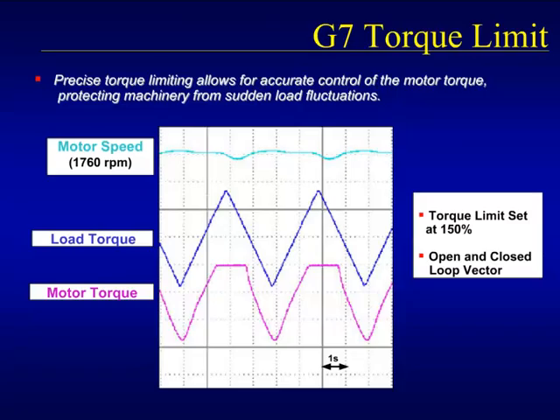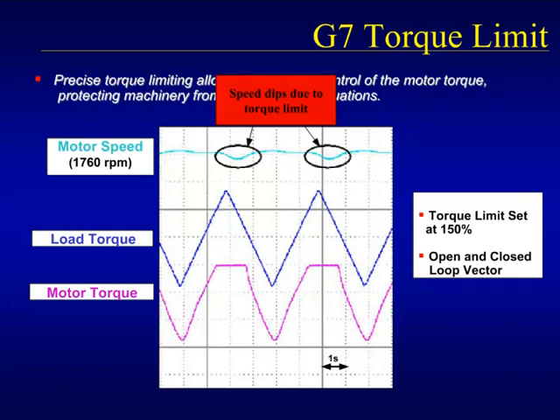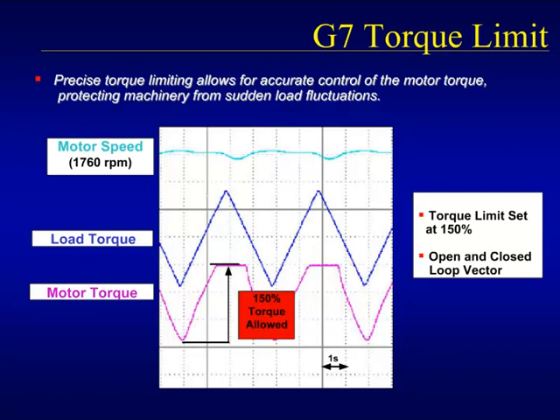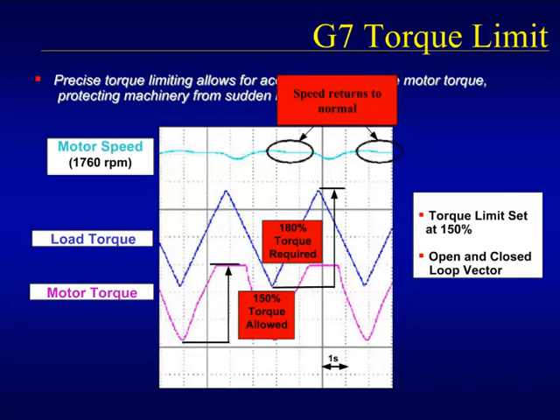Both vector modes of the G7 offer a 4-quadrant torque limiting function. While either motoring or regenerating, the G7 will precisely cap motor torque at a specified level regardless of the torque demanded by the load. The scope trace shows the motor speed dipping as the G7 limits the available motor torque to a level below the torque required to produce a constant speed. Once the load torque drops below the level of the torque limit, the motor speed returns to normal. The upshot of the torque limiting function is that the G7 can protect the powertrain equipment, such as couplings or gearboxes, or the application itself, from forces that can damage or destroy them.